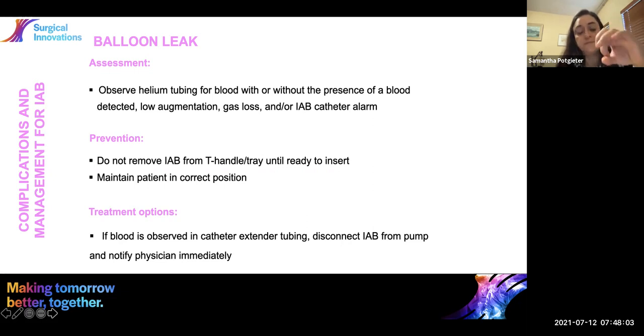So the risk with that is if there is in fact a leak in the balloon, it's usually minuscule, and you've got small amounts of blood that are now collecting inside the balloon. And each time it comes into contact with the helium that inflates and deflates the balloon, that blood dries out, and then you're looking at that entire, in the case of a 50 cc, that entire 50 cc eventually filling up and hardening. And there's absolutely no way you're going to be able to pull that catheter out as you would normally. That's a surgical cut down for that patient with a vascular surgeon's intervention, because you now have a 50 cc sausage, if you like, stuck in your patient's aorta.